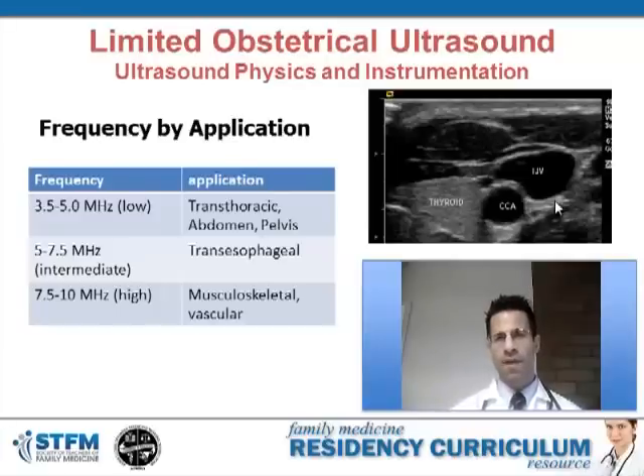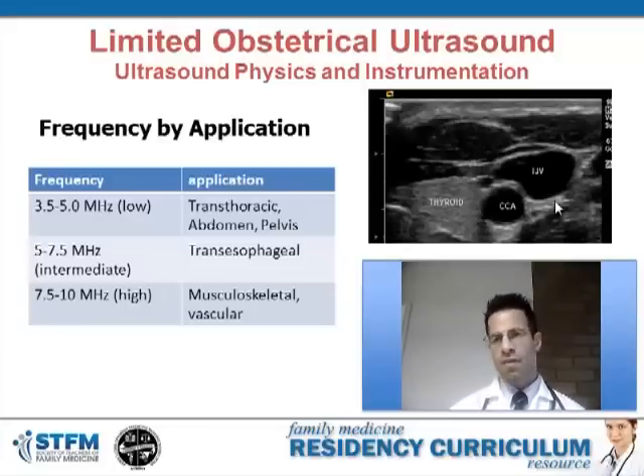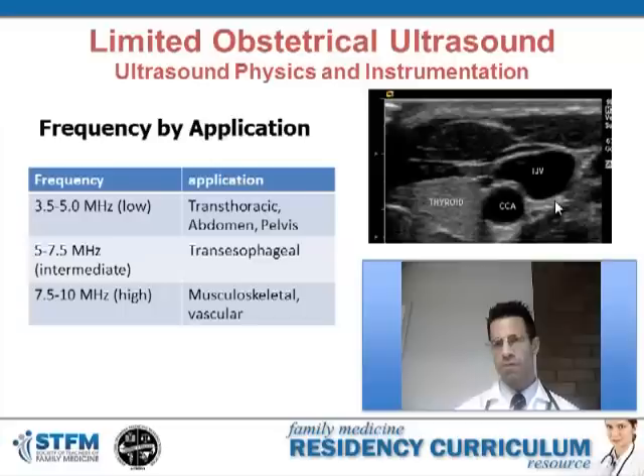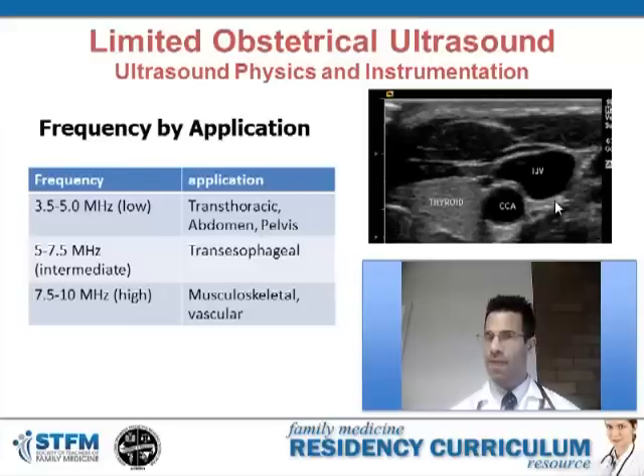Low frequency probes, typically in the range of 2 or 3.5 to 5 megahertz, are used when you need to image deeper, such as for transthoracic, abdominal, and pelvic imaging. Intermediate frequency probes, typically in the range of 5 to 7.5 megahertz, are most commonly used with transesophageal probes for cardiac imaging. Higher frequency probes, specifically 7.5 to 10 megahertz, are used when you don't need to image deep but high resolution is important.